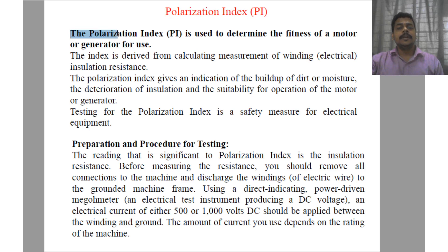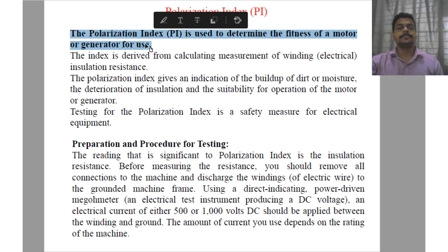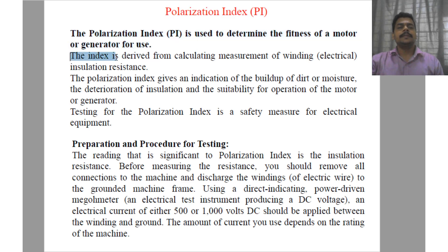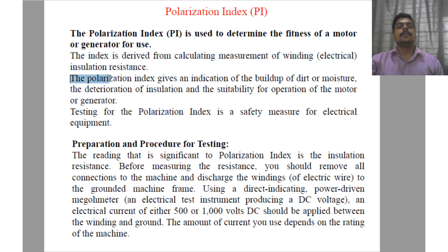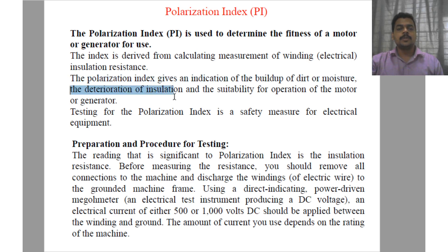The polarization index is used to determine the fitness of a motor or generator for use. The index is derived from calculating the measurement of the winding insulation resistance. The polarization index gives an indication of the buildup of dirt or moisture, the deterioration of insulation, and the suitability for operation of the motor or generator.